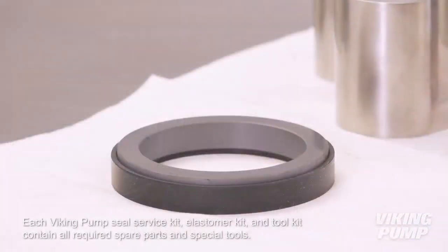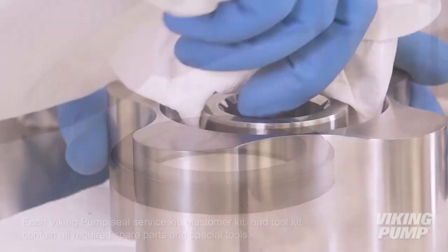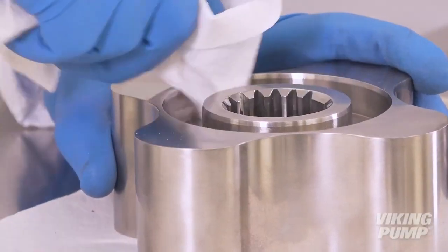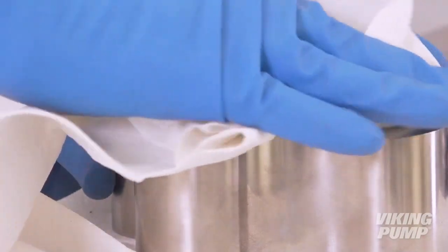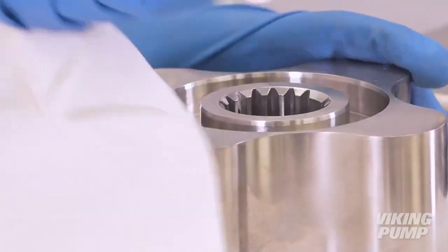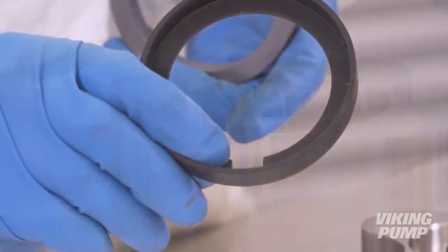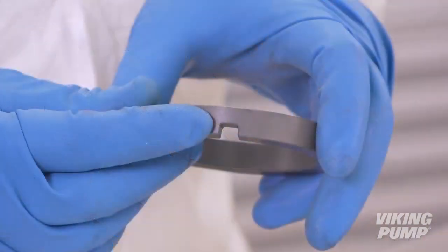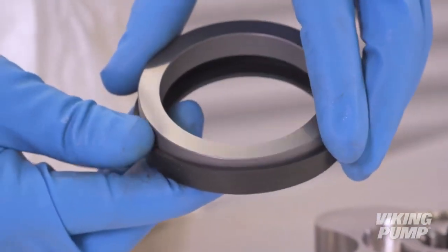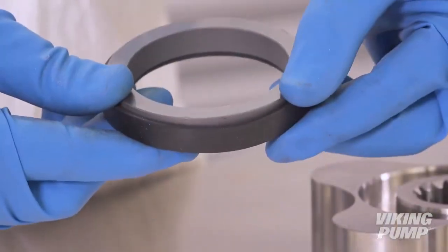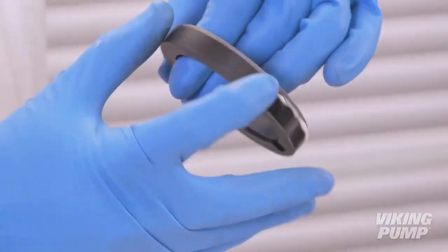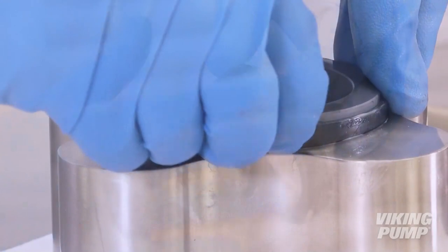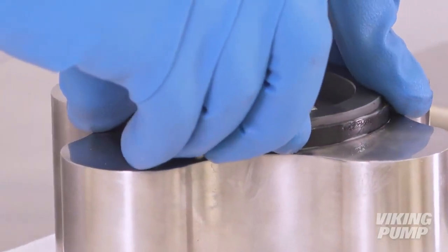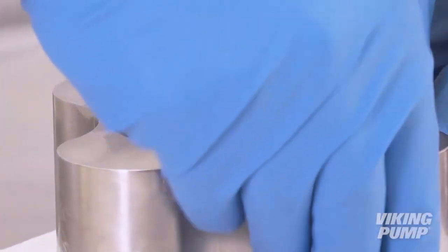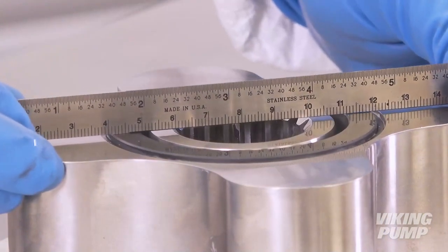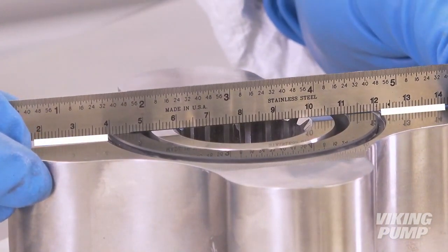Install new rotary seal faces and cups. To do this, place the rotors face down on a clean, non-marring work surface. Inspect the bore to make sure that it is clean and free from debris or damage. Line up the cutouts in the rubber cup and seal face. Lubricate the cup and press the seal face and cup into the rotor until it is fully seated. Make sure the face is level and parallel with the back of the rotor.